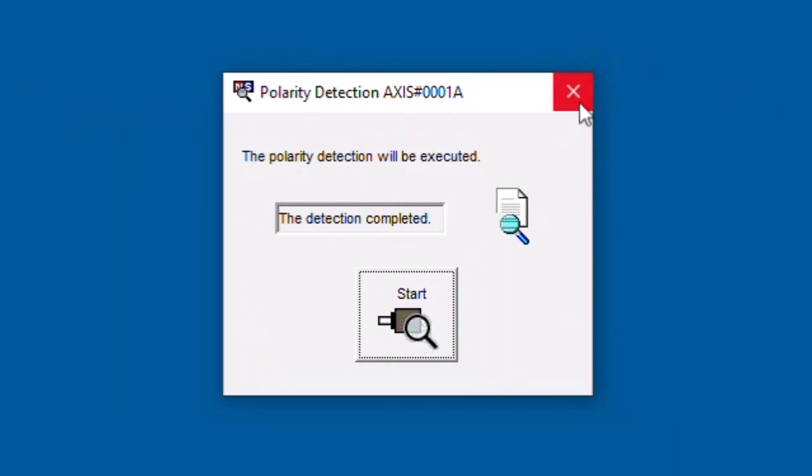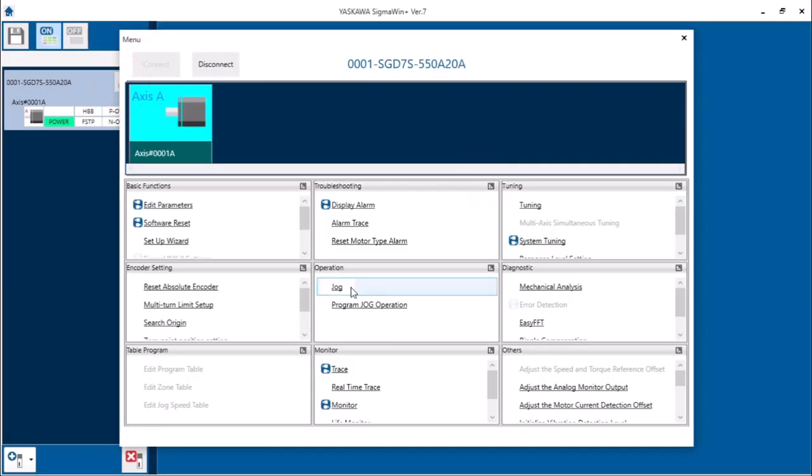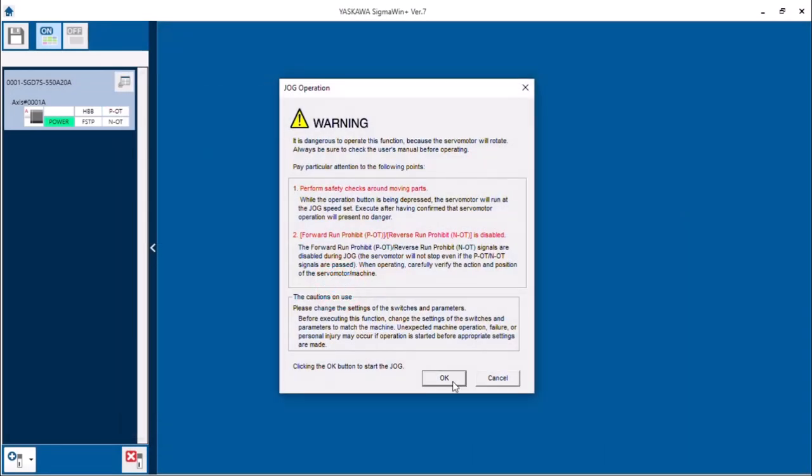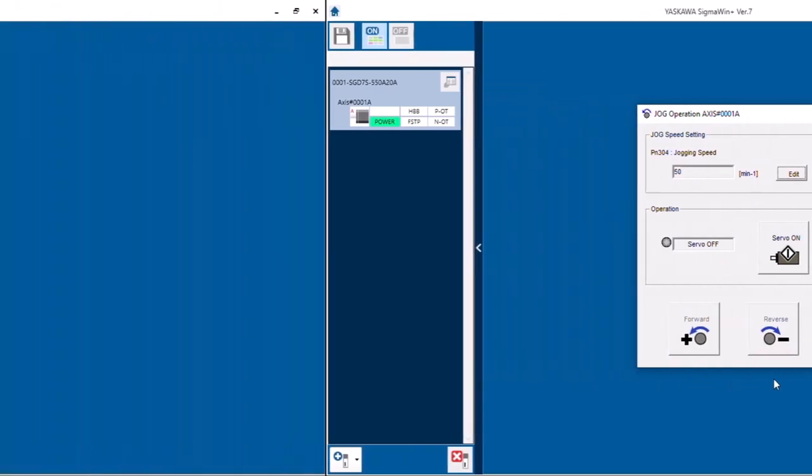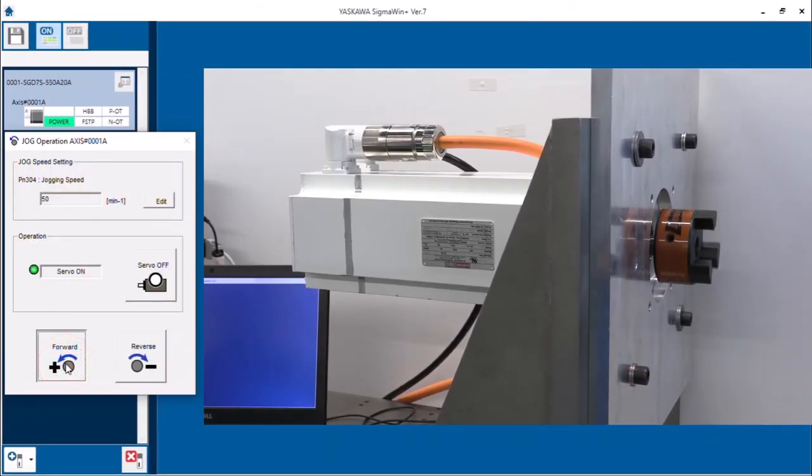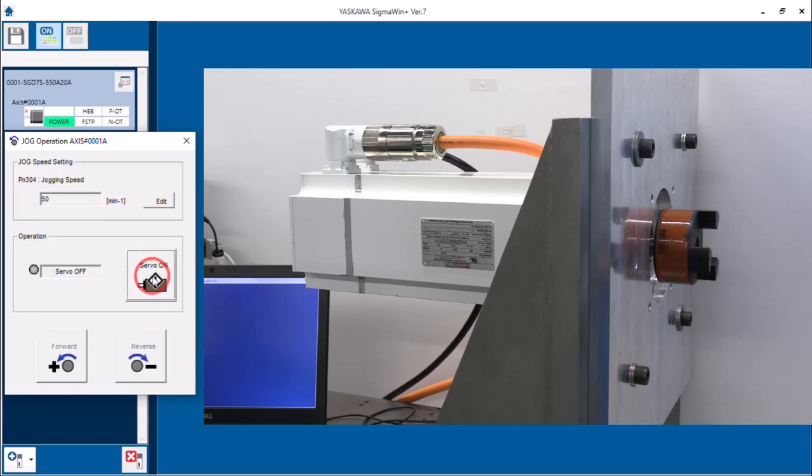Best practice is to cycle power to the servo pack after using polarity detection. So I'll do that. Real quickly I'll use the jog function to verify motor rotation is possible. Both forward and reverse. It looks good. So at this point you can continue to commission the machine.